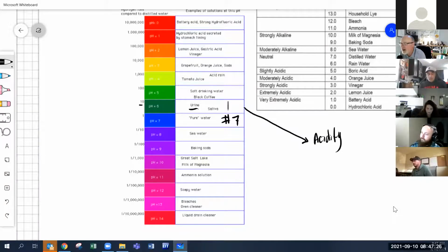That's why, because the high acid content will eat that copper drain. It reacts badly. That's why in commercial applications, it's either plastic or cast iron, right? On urinals, right? So that's why we have to do it. No copper allowed on drains for urinals.